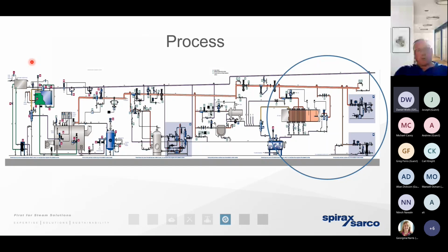And talking about the process, we also want to look at what we refer to as demand reduction. Demand reduction means that if we can use the steam or the thermal energy outside of the boiler house, outside of the energy centre more efficiently, then we're reducing the demand for steam. If we're reducing the demand for steam, we're reducing the amount of fuel that's required, and therefore we're reducing those carbon emissions. So one such process that's a little bit quirky, it is quite niche, but it does have its place in heavy industry, doesn't necessarily have to be coupled to a steam system. We can use other sources of thermal energy, such as hot effluent in the form of wastewater.